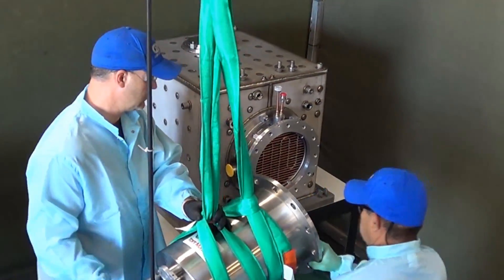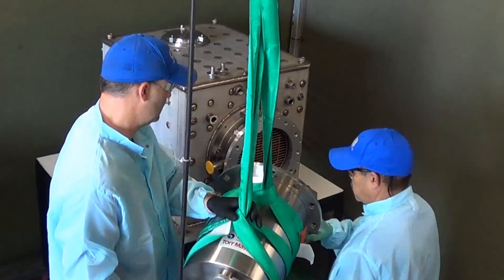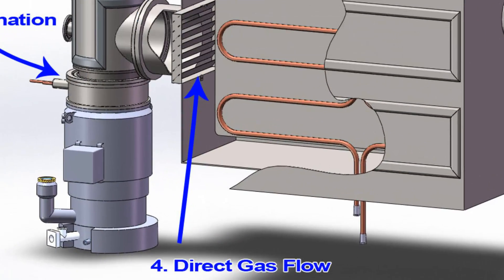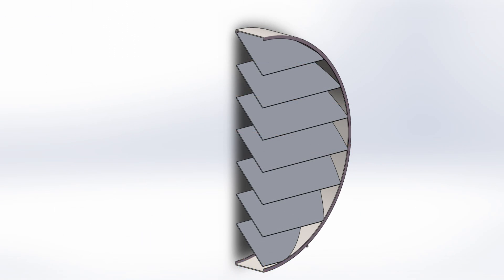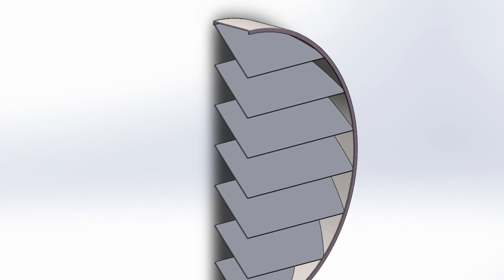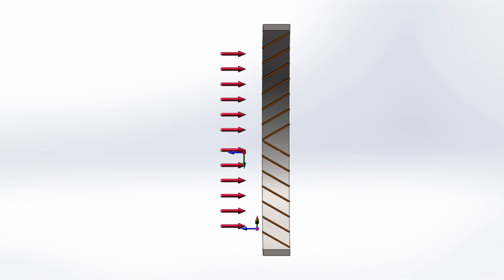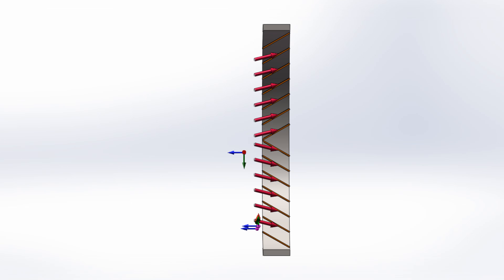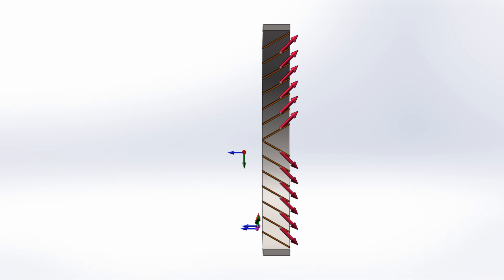The fourth use of a baffle is to direct the flow of gases. For this purpose, a baffle does not need to be cooled. The louvers of a baffle diffuser direct the flow during a rapid pump-down or during venting of the chamber, so the gas flow is directed away from parts and vacuum system components.